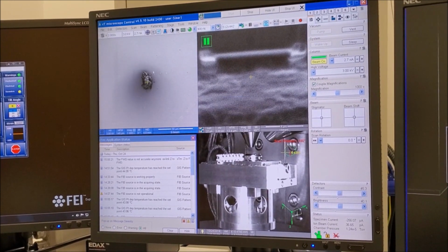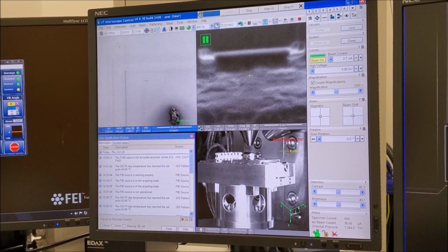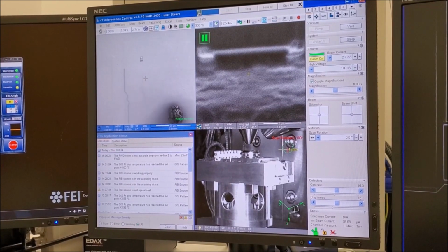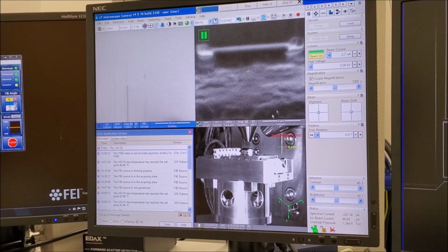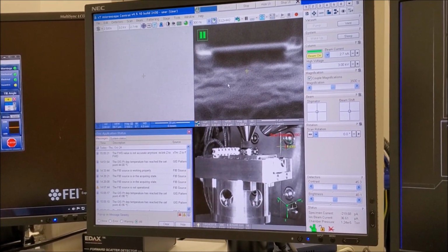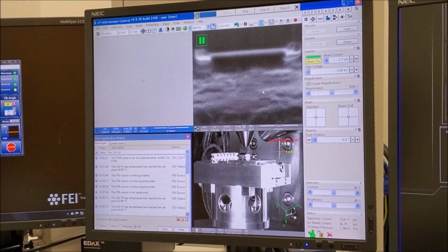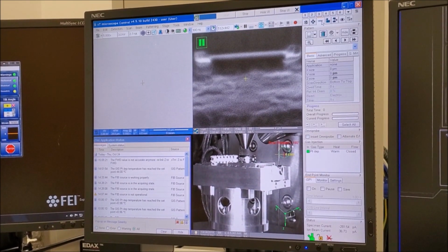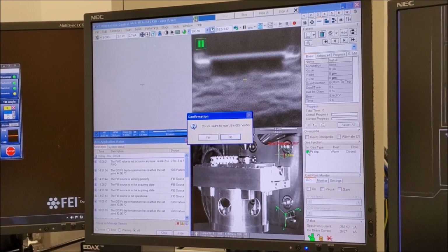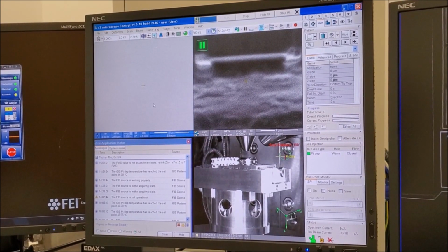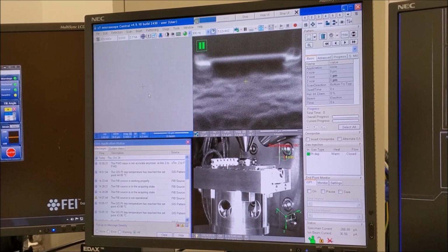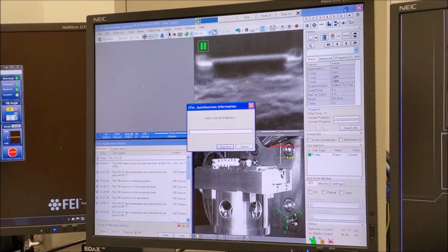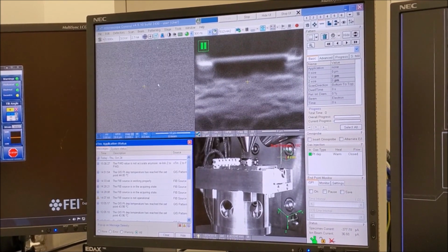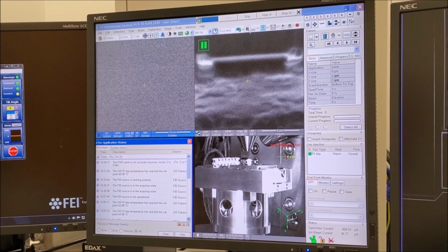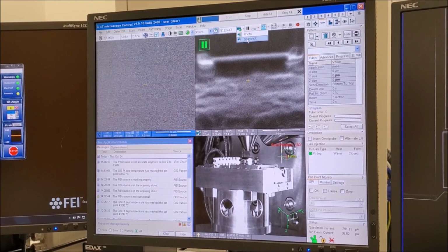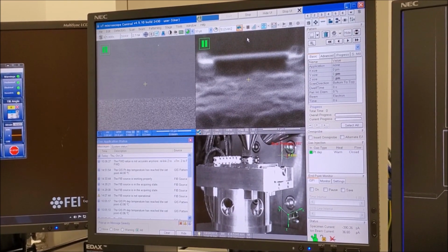With the stage set at eucentric height with a tilt set to 0, navigate to an area on the specimen that is free of debris. Set the magnification as needed, then navigate to the patterning module, then to gas injection, and then check the green box next to PT dep. The PT GIS will then insert, which will be accompanied by a change in contrast of the image, which can be corrected by using auto contrast and brightness. Then acquire a snapshot of the electron beam image.